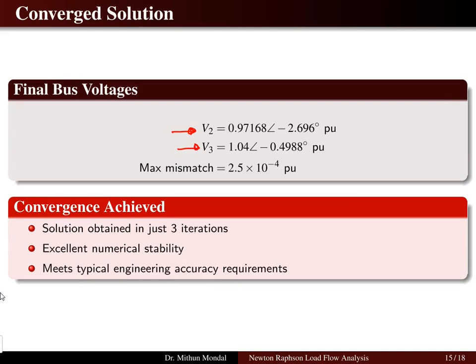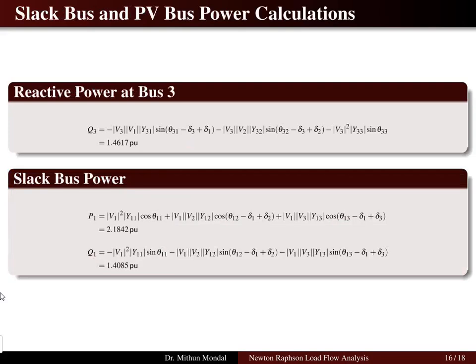The solution converges after the third iteration because the voltages are no longer changing. V2 and V3 — the final bus voltages — show a maximum mismatch of 2.5 × 10⁻⁴, which is a very small number. Convergence is achieved in three iterations with excellent numerical stability, and this accuracy meets typical engineering requirements.